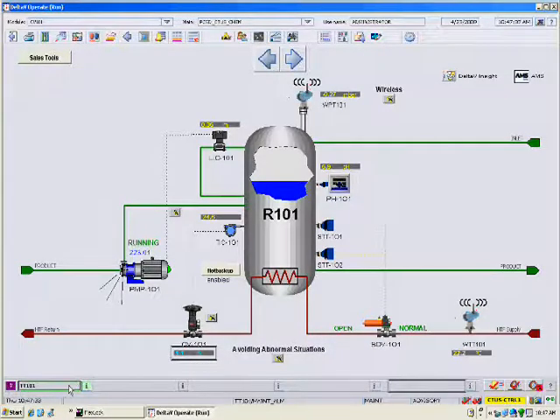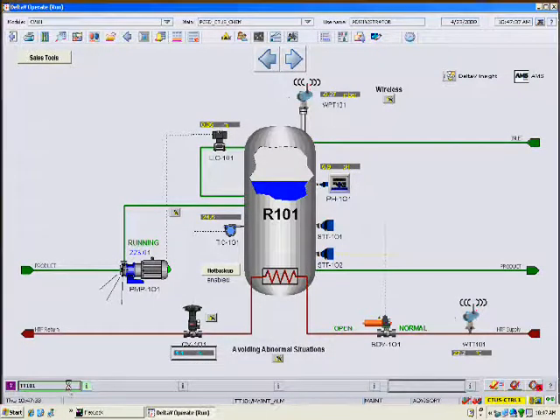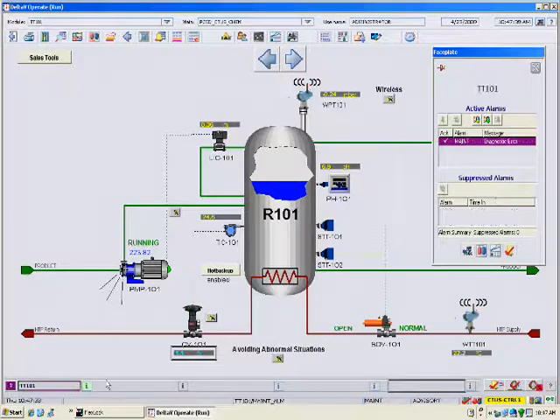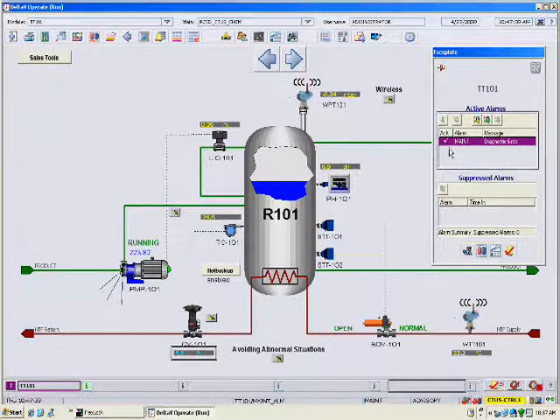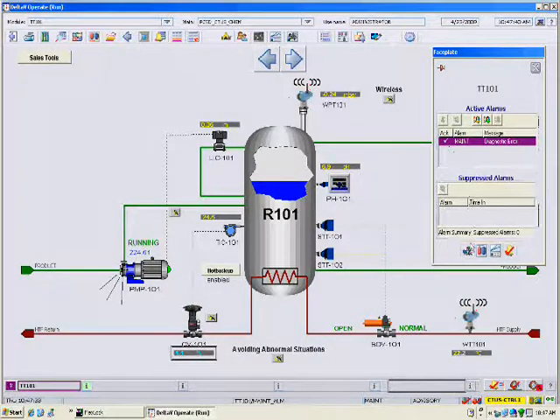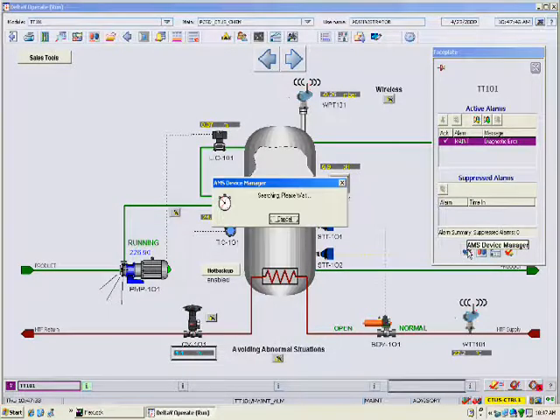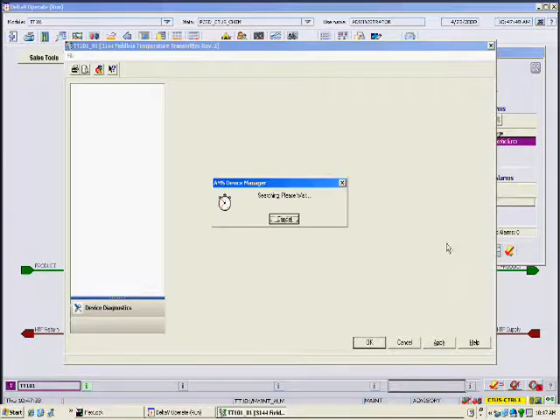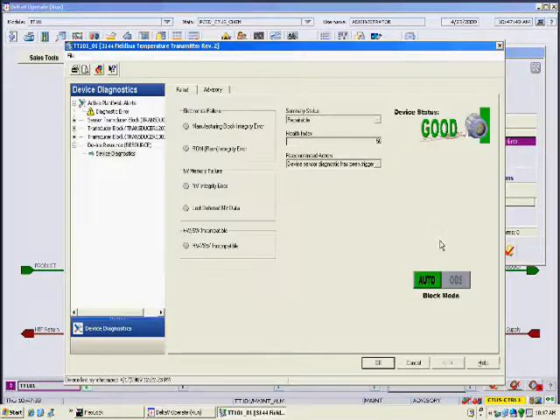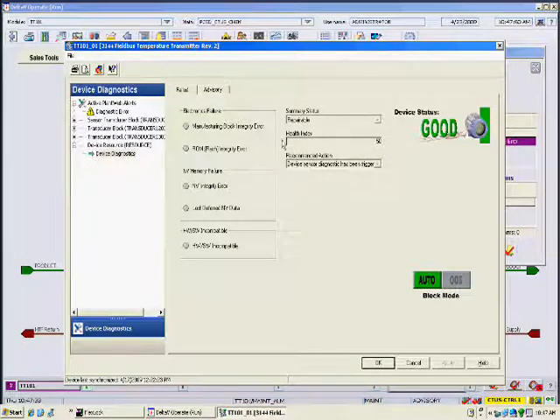The device alert appears and the operator clicks on the alarm banner, which opens the device faceplate. In this case, the faceplate shows it is a less serious maintenance diagnostics error. The operator opens detailed diagnostics at a click of a button without switching to another computer or software and without searching for the tag. The operator sees the device is actually still in good health, so the operator need not put the control loop in manual.